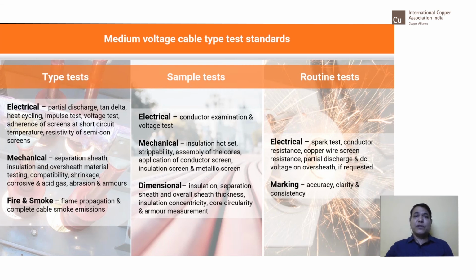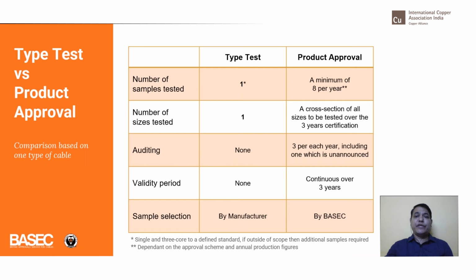Very important. Partial discharge test in the medium voltage cable should be done on every completed length, every dispatch length. So partial discharge is to ensure that the insulation is strong enough to withstand the high voltages for a long life. There are no leakages and all those things. So the difference between the type test and the product approval, which I said I will cover later.